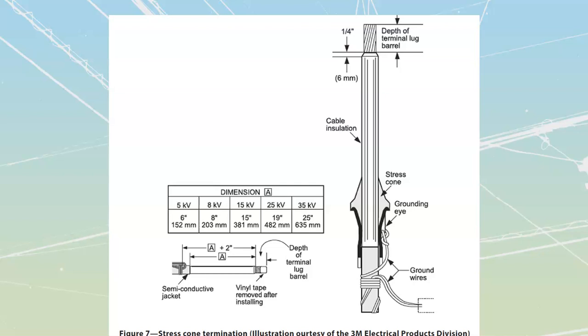For a 15 kV cable, we have to use this dimension. Dimension A is what we'd strip back on our cable, the distance between the insulation shield and the conductor itself. So I'm going to start by stripping back the insulation shield to the depth of my terminal lug barrel. Let's say I've got a 2-inch barrel. That means from the end of my cable I'm going to take a total of 15 inches plus this 2, so I'd strip back a total of 17 inches, from here to here.